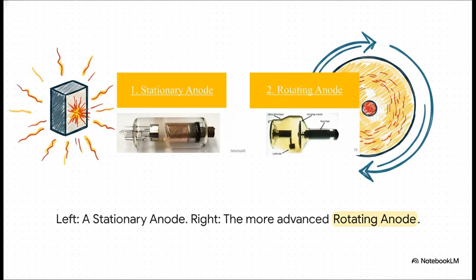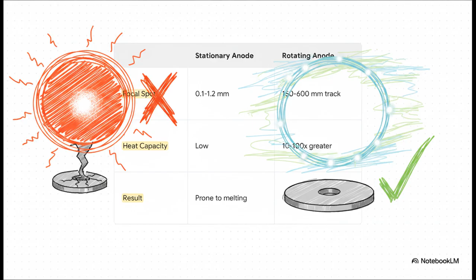The numbers here really tell the whole story. With a stationary anode, all that energy is blasted onto a focal spot that's sometimes just 1/10 of a millimeter wide. But by spinning the target, we spread that exact same amount of energy over a circular track that can be 600 millimeters long. The effective area is huge, increasing the heat capacity by up to 100 times. No more destructive hotspots. Here's a really simple way to picture it. Imagine you're trying to cook, but you're just holding a blowtorch to one spot on the frying pan. You just burn a hole right through it, right? Well, the rotating anode is basically the engineering version of constantly stirring the food or moving the pan around, making sure no single spot ever gets hot enough to cause damage.